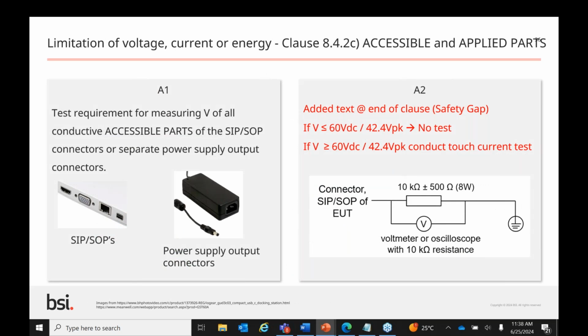Maintenance Team 28, Electrical Hazards, made an update to SIPSOPs, or what's known as IO, input-output requirements, in regard to 8.4.2. Before, the standard said to measure the voltage, and if the voltages were above a certain amount, then you need to do a test. Now, the way A2 is written in regards to accessible parts, if the voltage at the SIPSOPs or the power supply output connectors are less than or equal to 60 volts DC or 42.4 V peak, then no touch current test is conducted. And there's a method now in place for how to make the measurement if the voltage is greater than or equal to that amount. You conduct the touch current test. Additionally, you need to test that the energy does not exceed 240 VA or 20 joules at a potential of 2 volts or more. Next slide, please.